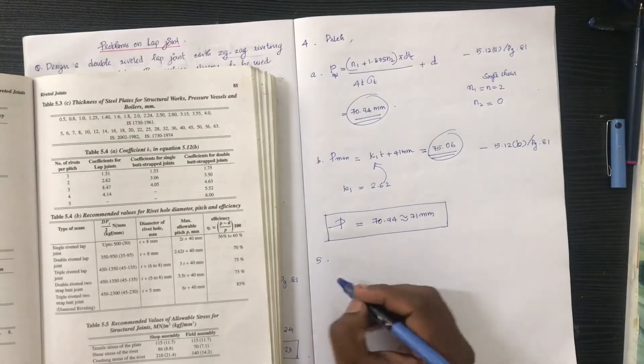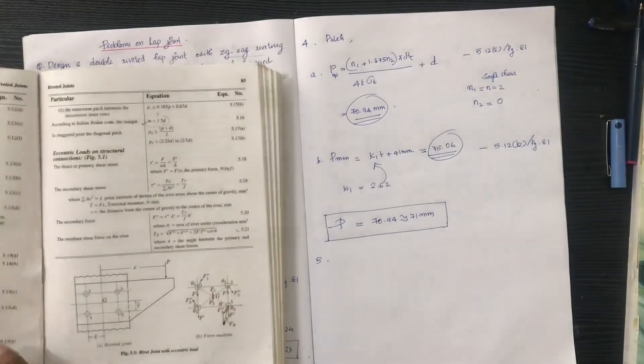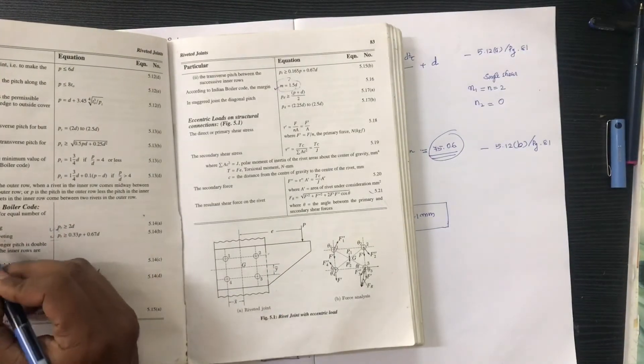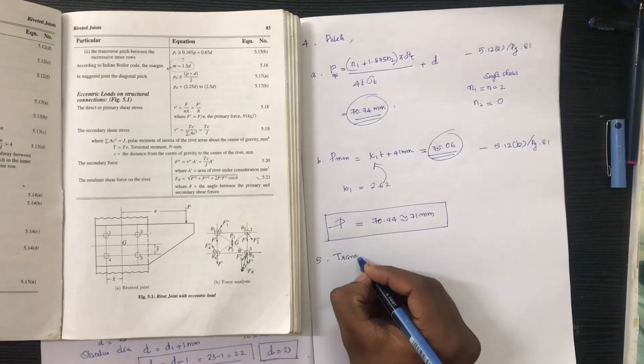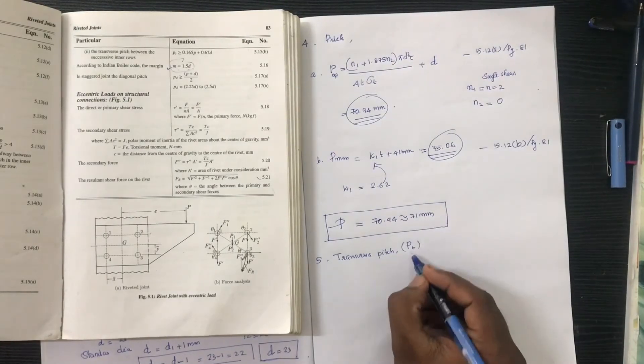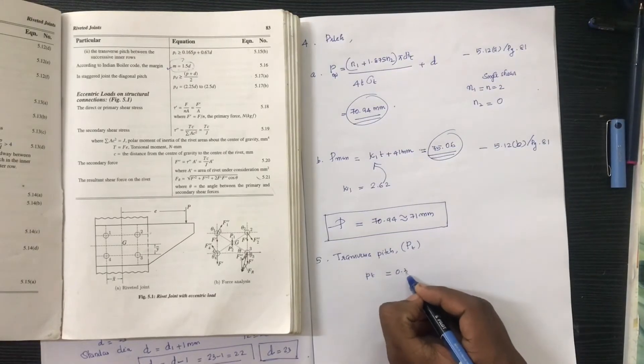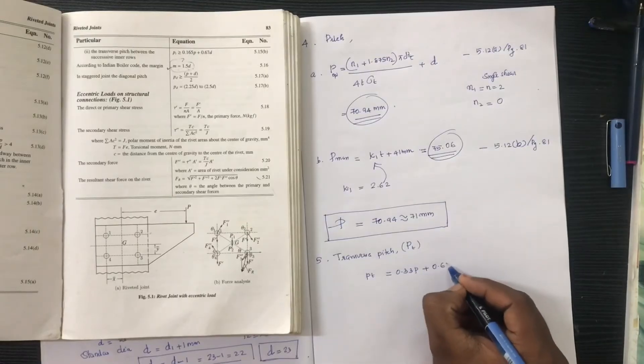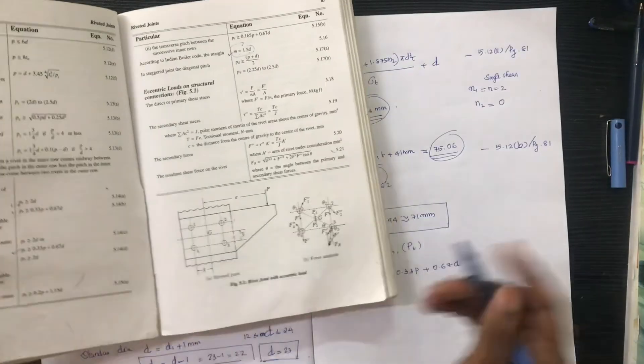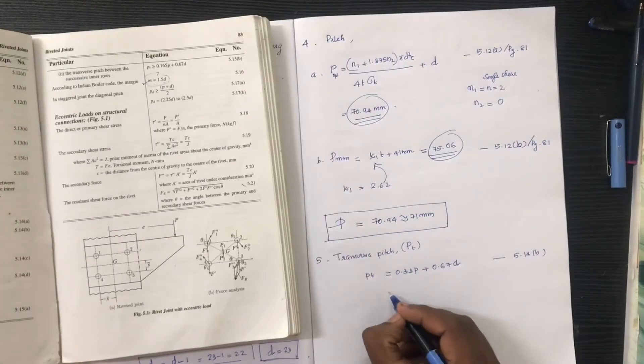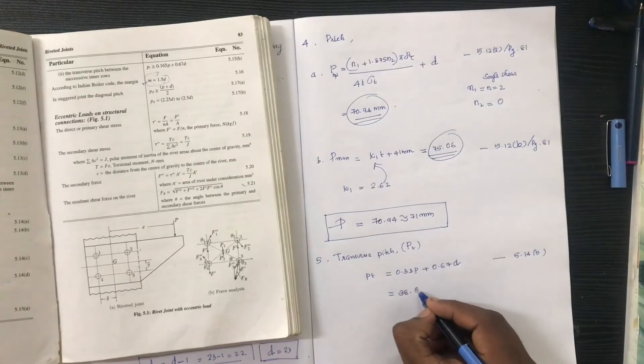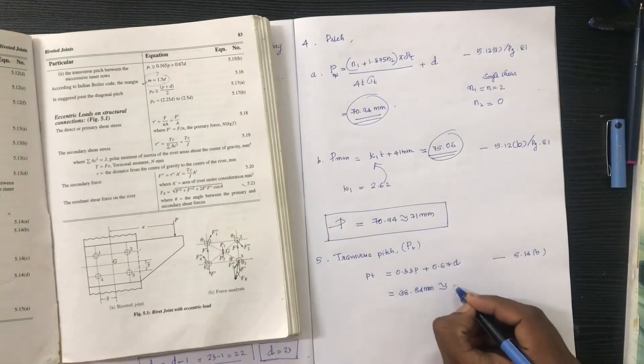The design for pitch also requires the transverse pitch. According to the Indian Boiler Code, for staggered or zigzag riveting, the transverse pitch Pt is equal to 0.33p plus 0.67d. For chain riveting, Pt equals 2d. That is formula 5.14b. Substituting values gives approximately 38.84mm, which is rounded to 40mm.